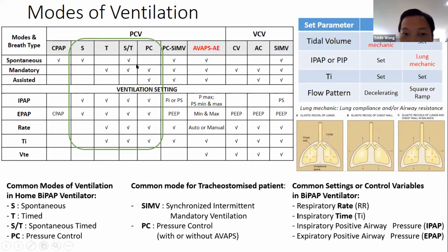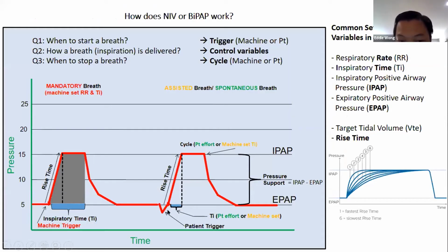Maybe that time the doctor will change your mode to ST mode, to pressure control mode, so that when the machine delivers, when you trigger a breath, the cycle time to end the breath will follow the I time, so that you have more time to breathe in more air or more oxygen. So I hope my explanation is able to explain the difference between mandatory, assisted, and spontaneous here. It's a bit technical, but you can watch the replay later if you want to come back to this section.